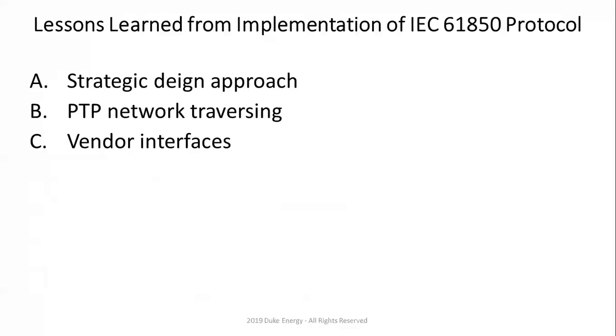And the vendor interfaces. So why do we do 61850? As you probably know, when you do typical protection, you have to run a lot of copper wires from the yard over to the substation. That's a lot of copper, right? And also the biggest challenge is how do you make sure that those copper wires stay there? How do you make sure you don't have an open CT circuit, et cetera?